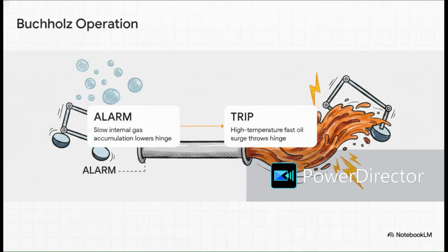And it operates in two perfectly escalating steps. Let's say there's a minor internal fault. It slowly burns the oil, creating these little gas bubbles that naturally float up the pipe and right into the Buchholz relay. This slow gas accumulation gently lowers a float hinge inside, triggering an alarm. But if there's a massive, violent short circuit, the extreme heat creates a fast, forceful surge of oil straight up that pipe. That physical wave of oil violently throws a second hinge, instantly sending a hard trip signal to the breaker. It escalates beautifully, based entirely on severity.